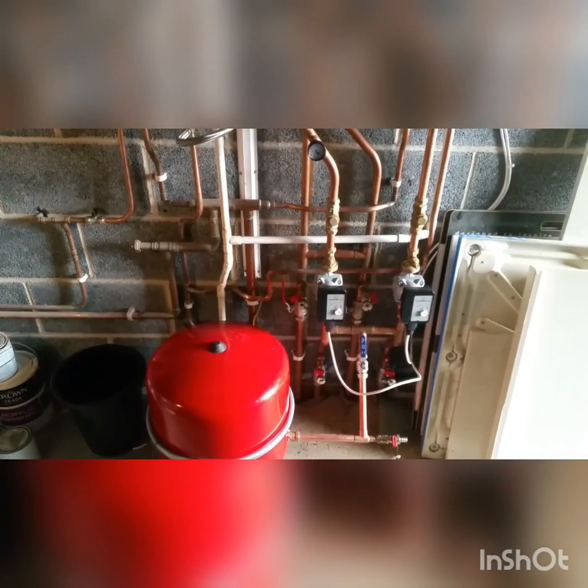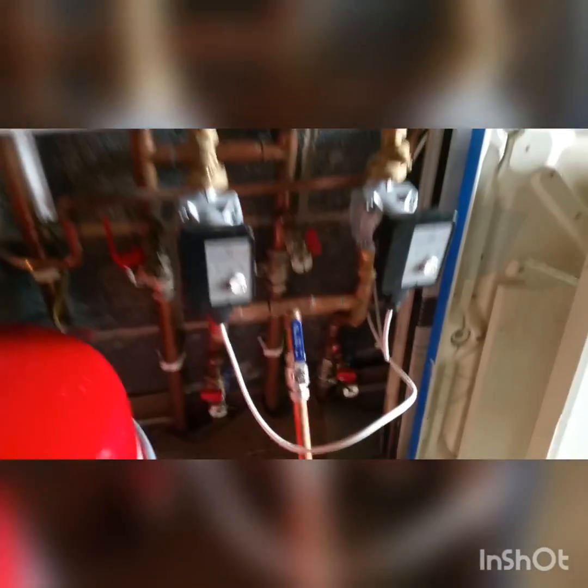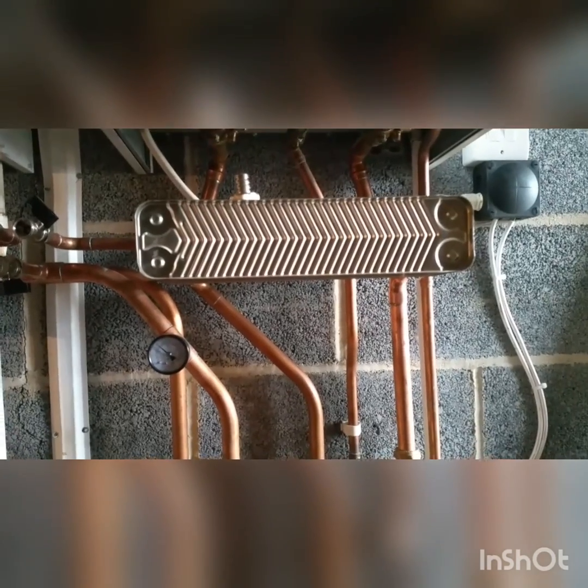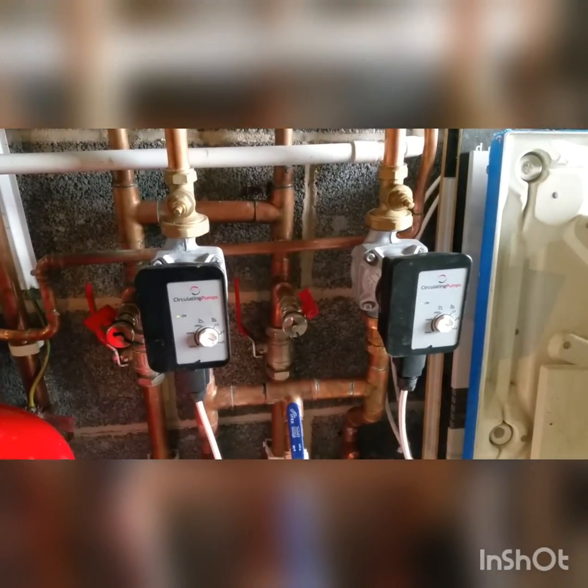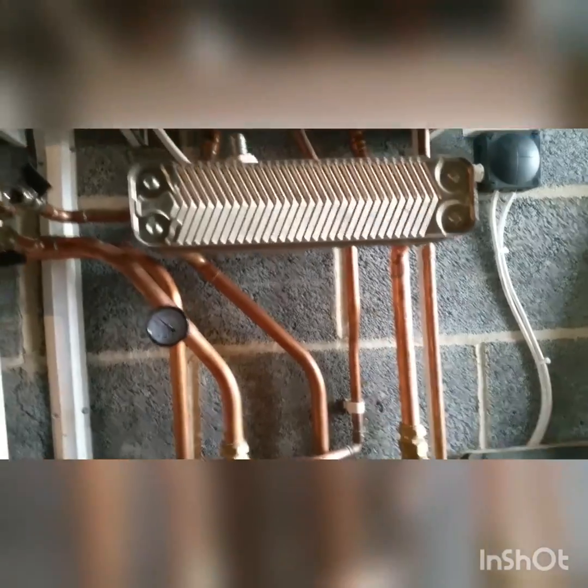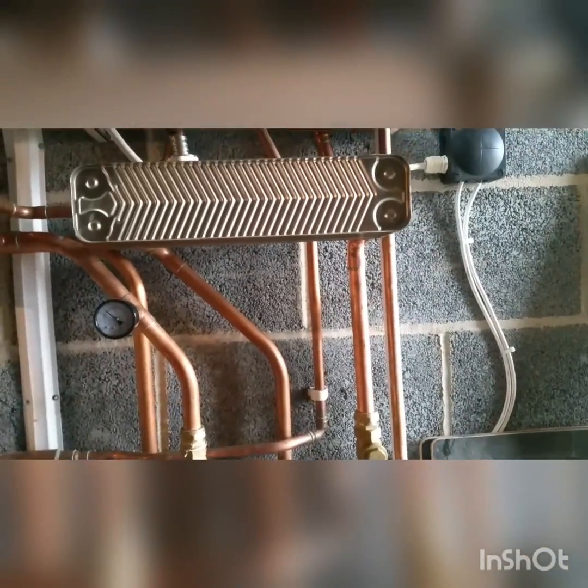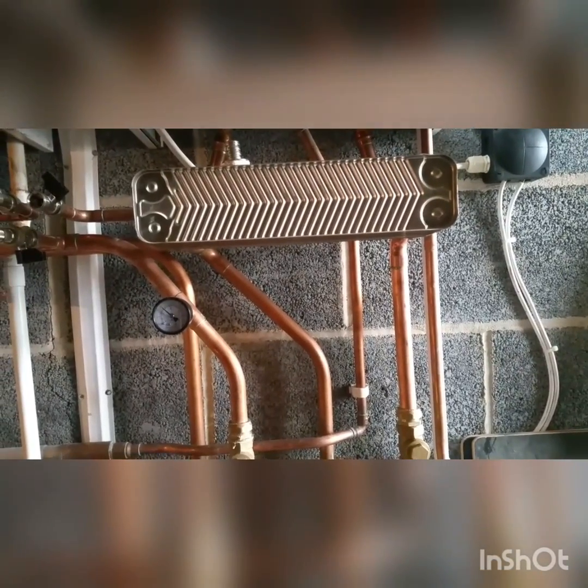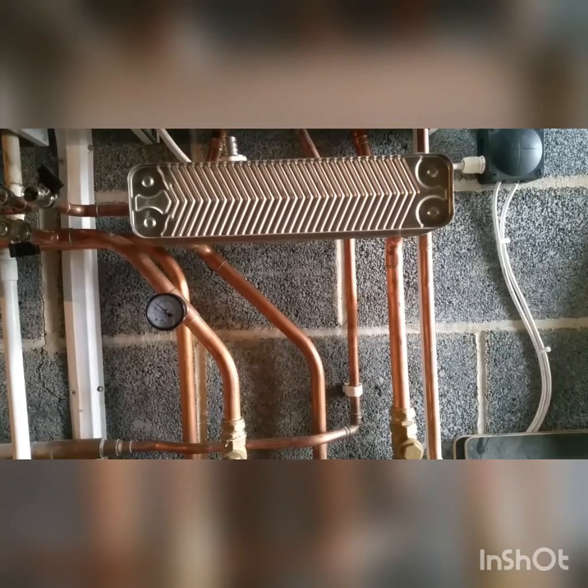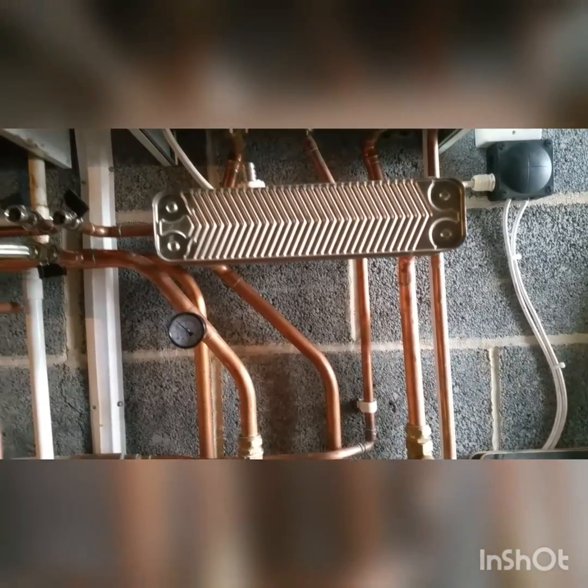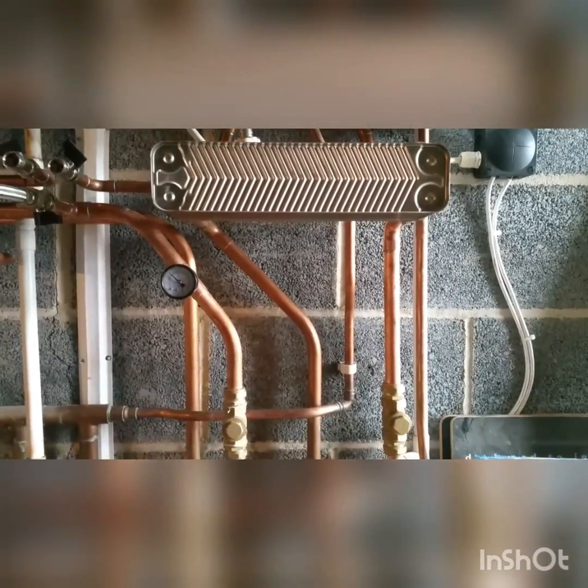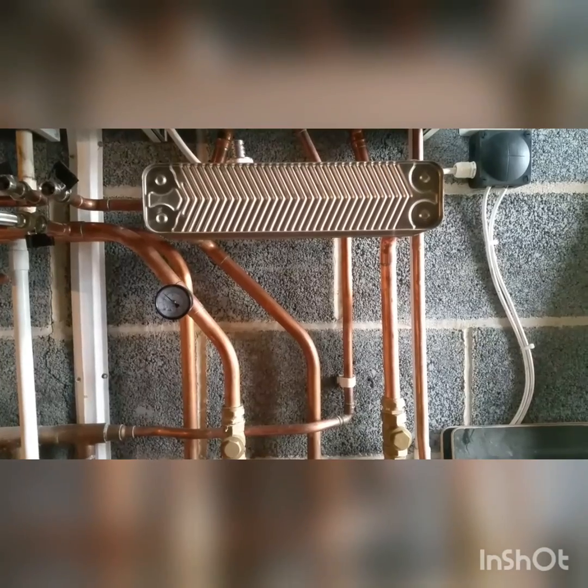So I've done plate separation on each boiler and connected them together down at the bottom here to go off to my system. So what I did here, but normally I would put the pump on the flow from the plate heat exchanger, but I read somewhere recently in the last few weeks that you should always pump towards the biggest restriction in a system, so the point at which you get the greatest pressure loss, which I suppose is logical. The idea is to reduce the risk of cavitation, I guess, or to keep a majority of the system under a greater positive pressure, if that makes sense. I hope you understand what I'm trying to say. So that's what I've done.